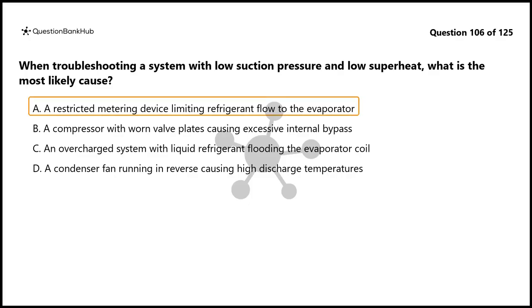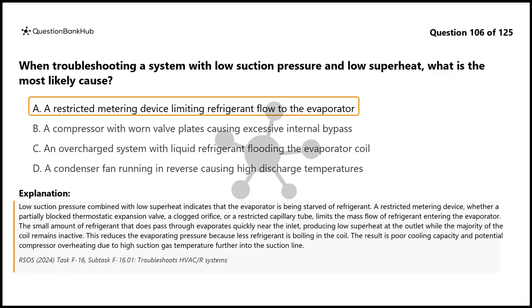The correct answer is A. Low suction pressure combined with low superheat indicates that the evaporator is being starved of refrigerant. A restricted metering device, whether a partially blocked thermostatic expansion valve, a clogged orifice, or a restricted capillary tube, limits the mass flow of refrigerant entering the evaporator. The small amount of refrigerant that does pass through evaporates quickly near the inlet, producing low superheat at the outlet while the majority of the coil remains inactive.